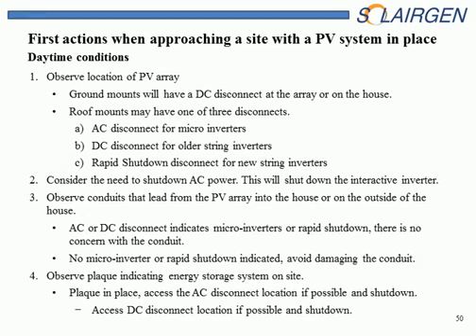A roof mount may have one of three disconnects: AC disconnect for microinverters, DC disconnect for older string inverters, rapid shutdown disconnect for new string inverters. So these are the disconnects that you would see for a roof mount system. Consider the need to shut down the AC power. This will shut down the interactive inverter, so all AC power is down and there's no conversion going on. There's only potential energy at this point.